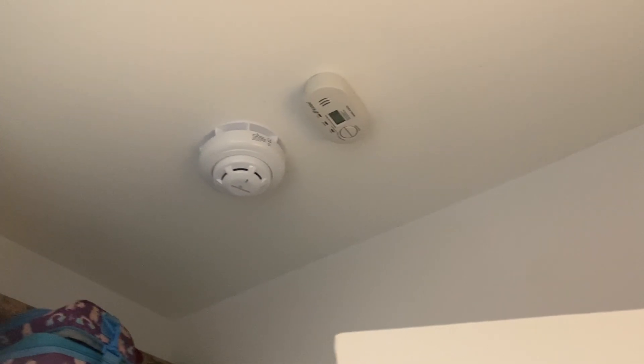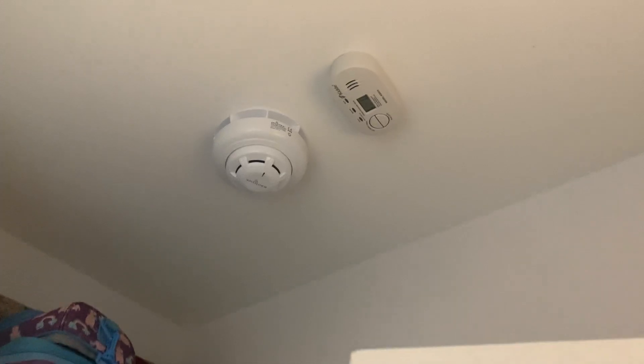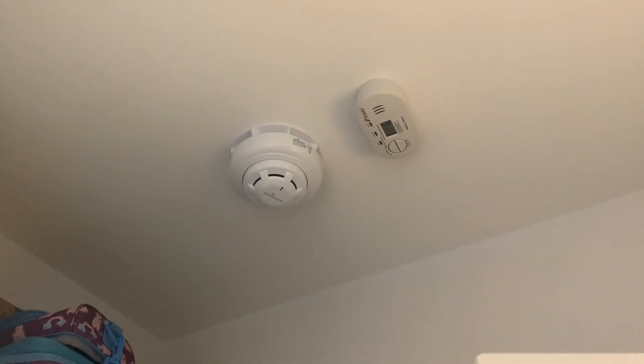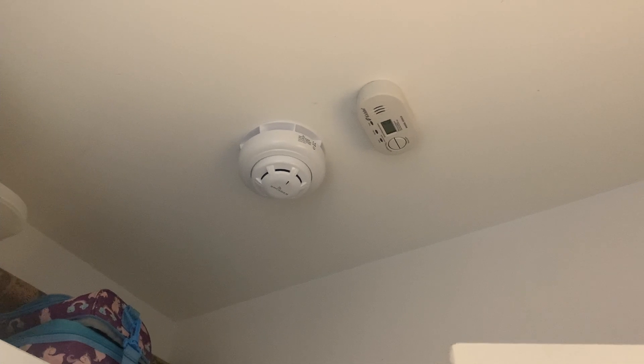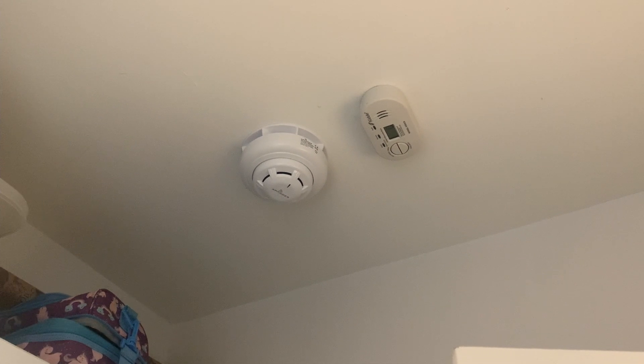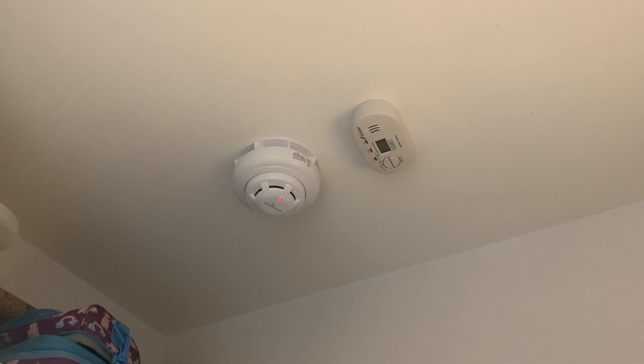Now we're moving on to testing the expander optical and also the call point under the cupboard. The system is in test mode — I've activated test mode for this zone. Let's spray it now. There we go, it's probably gone into pre-alarm. There we go — that worked well.